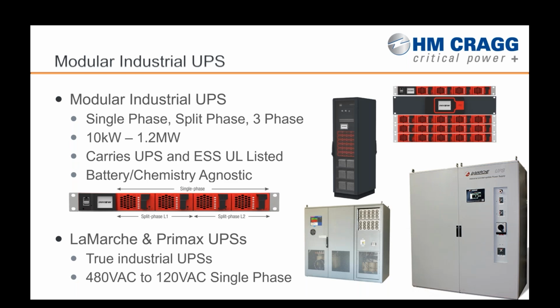They can do single phase, split phase, or 3-phase configurations. What we've found is a kind of cutting edge capability for CE+T is these power systems carry both a UL listing for UPS 1778 as well as the UL listing for energy storage systems, which is 1741 SB. So there's a value sale to be had on this UPS system that can directly inject power back to the grid. The last neat bullet point is they're battery and chemistry agnostic, so as long as you can support them with their DC bus voltage, they don't really care what source it's coming from. It can be lead acid, lithium, or hydrogen. As long as it's that DC bus voltage they're looking for, it's compatible.